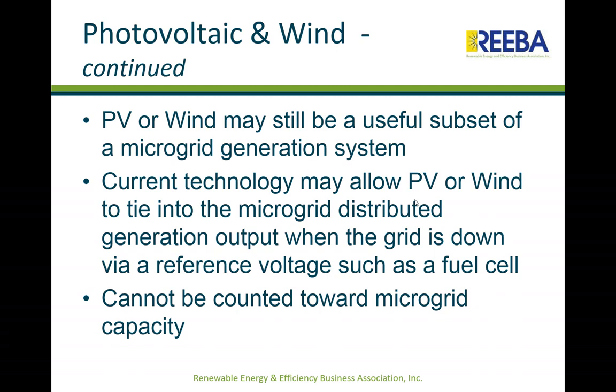Under current technology, you can, for example, integrate a solar system into the microgrid by using a reference voltage, such as a fuel cell. So if the system gets islanded, you can still run the PV or wind under island mode, as long as you have that reference voltage, including a fuel cell.